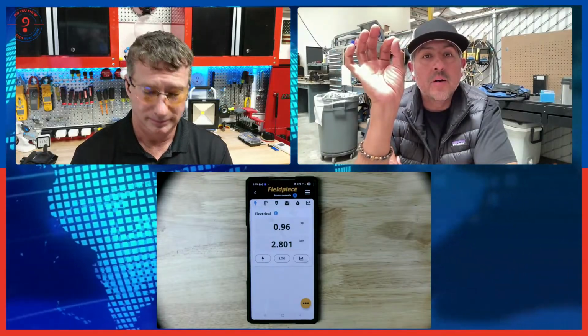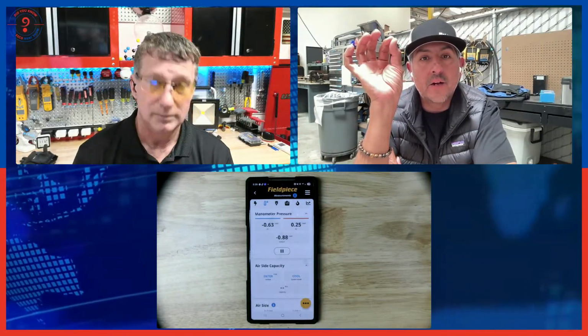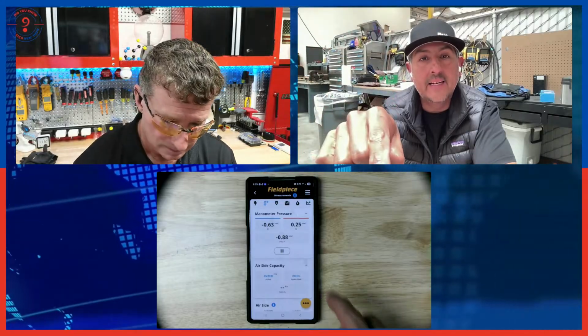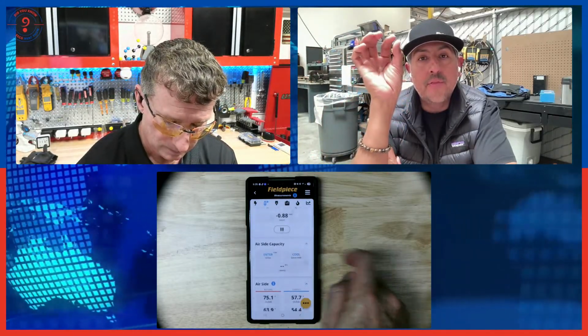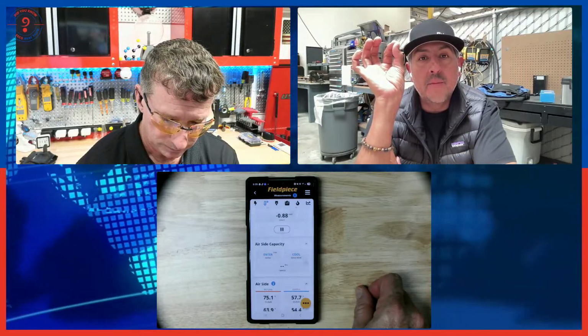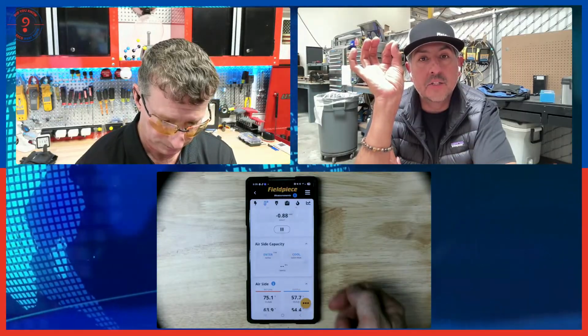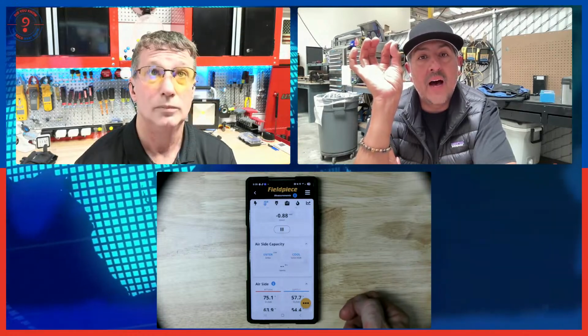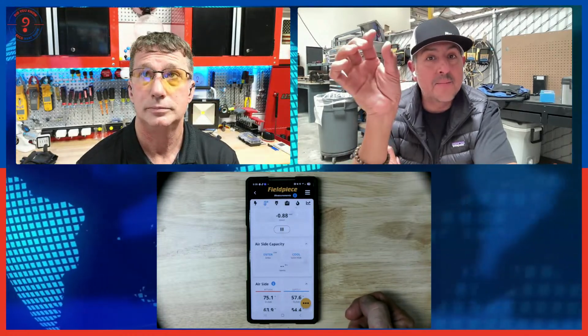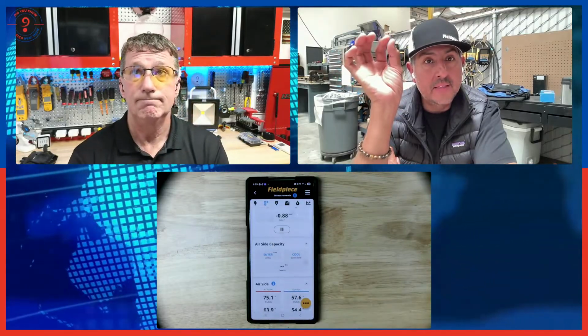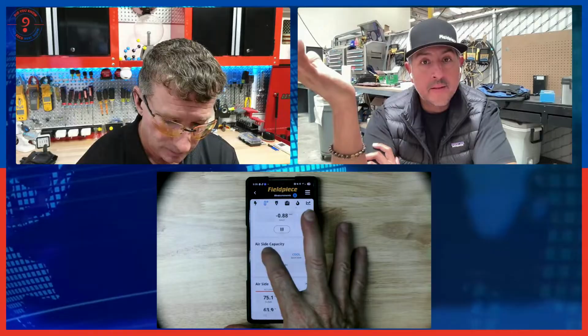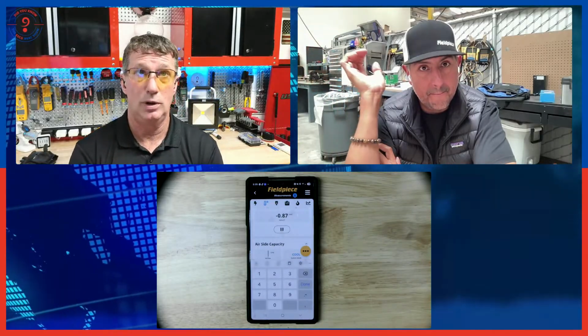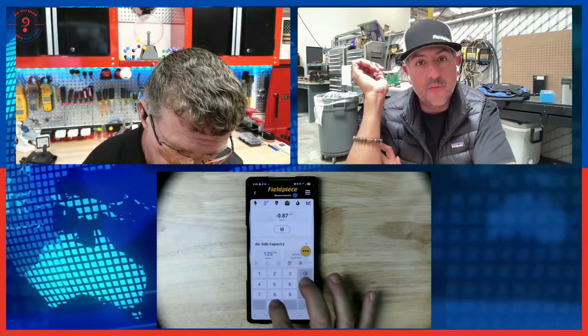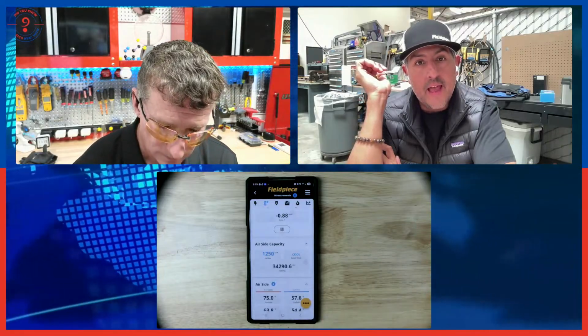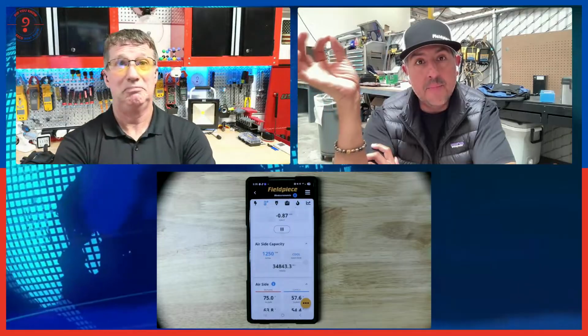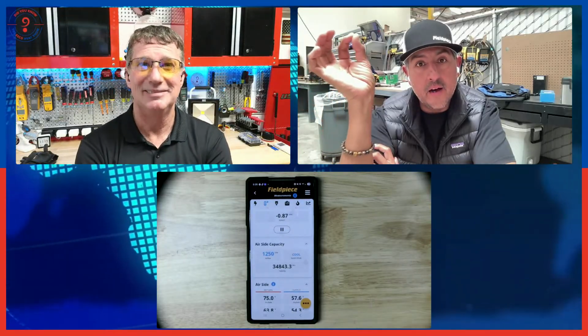What can we determine from the data? If you go back to the thermometer, we can quickly show how to do the capacity. The air side capacity is that container right there. It needs the measurements from the psychrometers because it looks at delta T to measure capacity, and it needs a CFM value. For the sake of time, we can estimate the CFM of that piece of equipment. You said it was 3 ton? Yes, it's a constant torque set at about 1250. Okay, let's insert 1250 in there. Now we have a real-time BTU cooling capacity. Look at that.